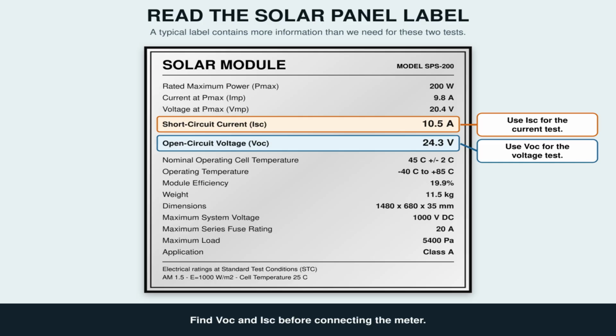Before connecting the meter, start with the label on the back of the panel. A normal solar panel label contains several ratings, but we only need two for this lesson. VOC is the open circuit voltage. That is the number we use for the voltage test. ISC is the short circuit current. That is the number we use for the current test. Our example panel is rated at 24.3 volts VOC and 10.5 amps ISC.